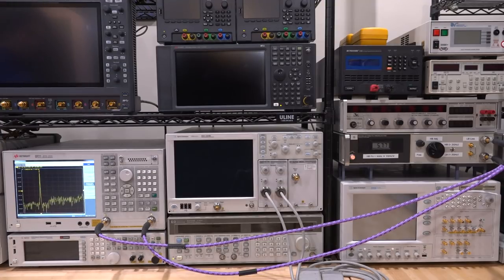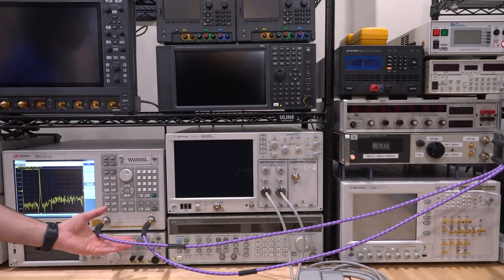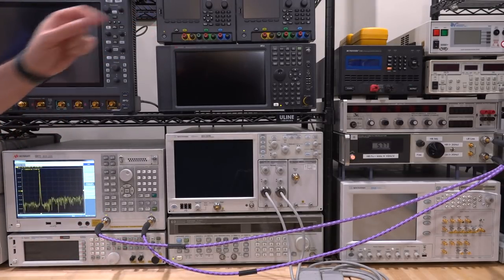All right, so here's the second puzzle for the viewers. Here on the left side, we have a Keysight E5071C. This is an ENA series network analyzer. This one goes from 300 kHz to 20 GHz. It's already been calibrated using an electronic calibration module, and I have port 1 and port 2 connected to that instrument all the way on the right.